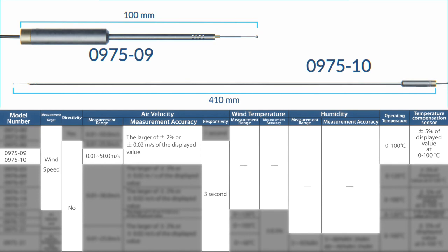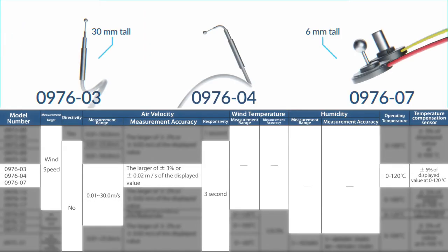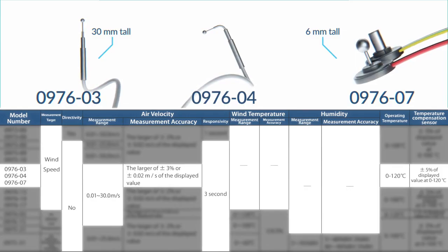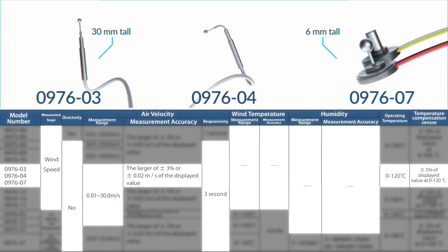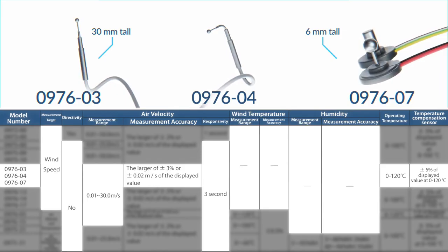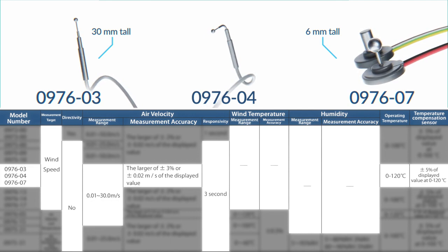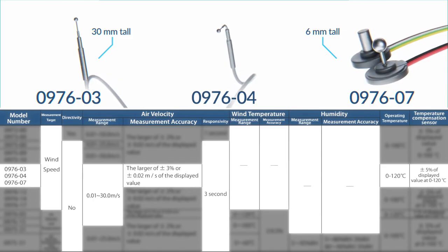Model 0975-10, on the other hand, also shares the needle-type tip, but it's over 4 times the length of the other needle-type models, making it ideal for those occasions when a longer reach is needed. Models 0976-03, -04 and -07 are heat-resistant omnidirectional probes that measure air velocity within a range of 0.01 to 30.0 meters per second. They're accurate to the larger of plus minus 3% or plus minus 0.02 meters per second of the displayed value, processed every 3 seconds, and operate at temperatures from 0 to 120 degrees Celsius.